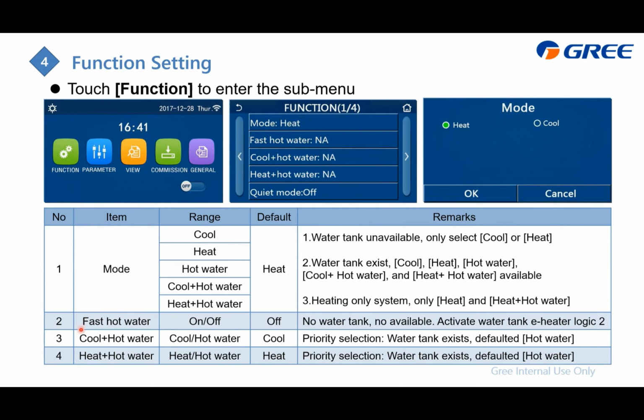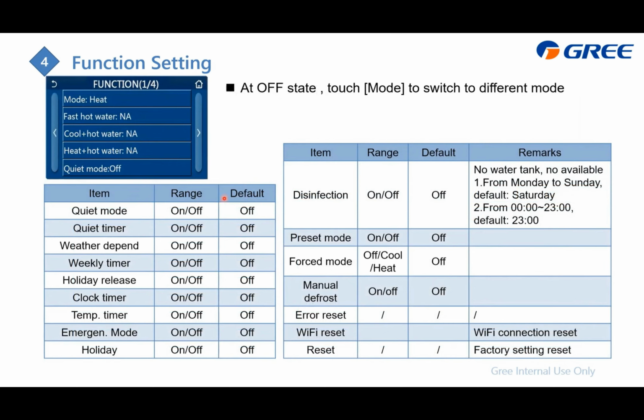And the next is the fast hot water. This is to achieve that the heat pump and the water tank heater can work together to heat up the DHW. And of course, please activate the water tank heater at the commissioning setting. And the next is to select the priority for the combination. At the second page, according to the name, you can find out its meaning, just activate or deactivate the functions.